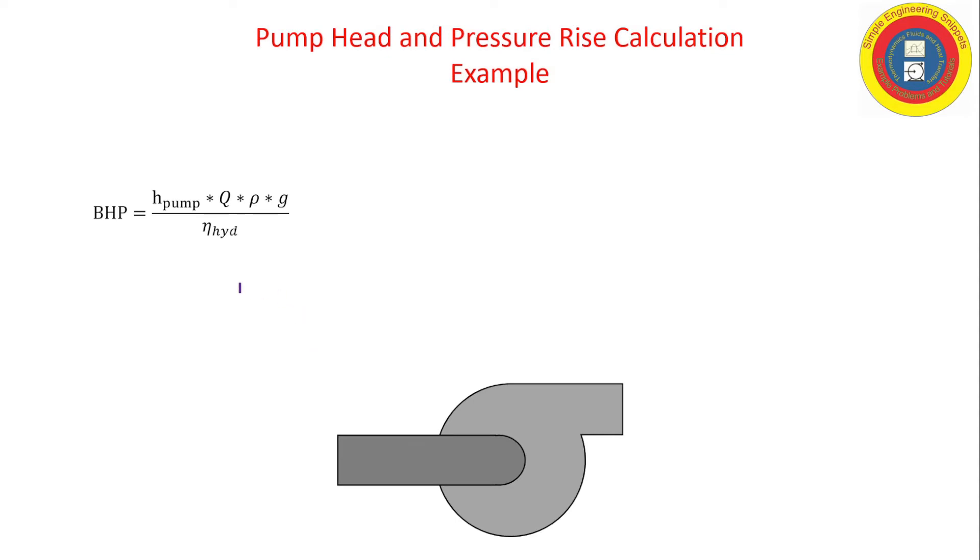Okay, so one of the things that we're provided is the brake horsepower. Here's the equation for brake horsepower. In the numerator, this is the amount of energy or power that is actually provided to the fluid. The pump is not perfect, and so we divide through by the efficiency to obtain the brake horsepower. The brake horsepower is the power going to the shaft of the pump, that power is provided by typically a motor, maybe a turbine.